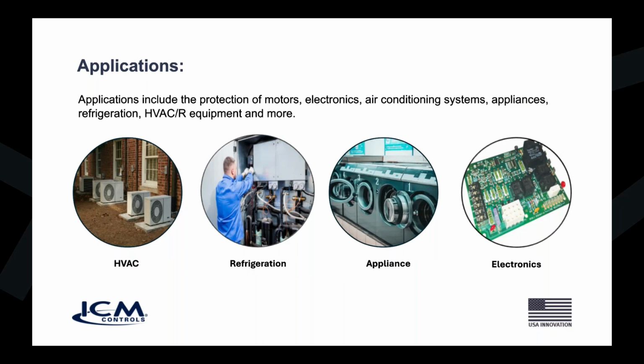Appliances, all your appliances, these days almost every appliance has some type of electronic board in it. Having one of these surge suppressors on a breaker that's feeding that piece of equipment can save those circuit boards from getting damaged. And of course, electronics such as the furnace board on your furnace, your defrost boards, or other boards on your heat pumps or HVAC equipment, and any other electronic boards that you might have in some other equipment. Single phase surge protection for residential applications and light commercial is pretty much required these days.